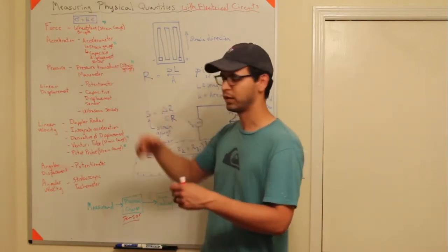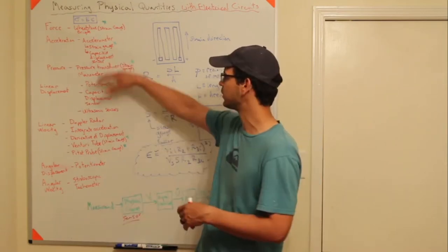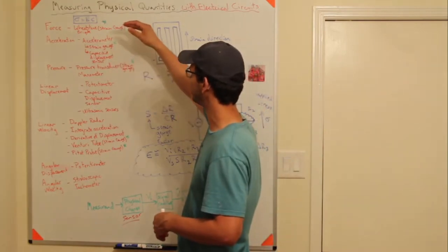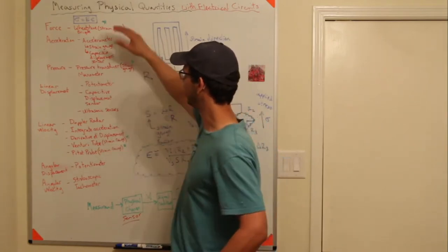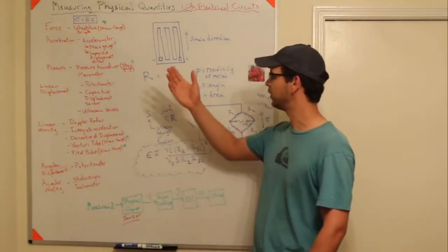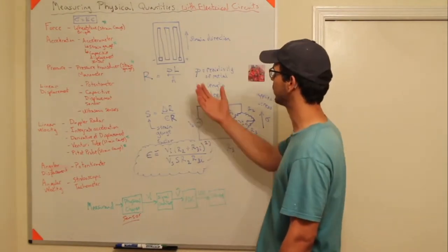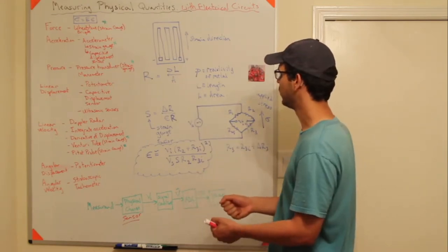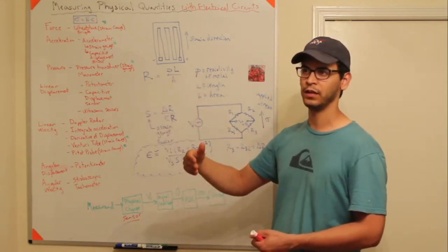You can combine strain gauges with other things — like accelerometers, you can have a pendulum that swings. Strain gauges can be used in multiple different places. The strain gauge by itself doesn't measure a physical quantity other than strain. In order to get force, you have to measure strain and then multiply by E, Young's modulus, to get stress — and stress is force divided by area.